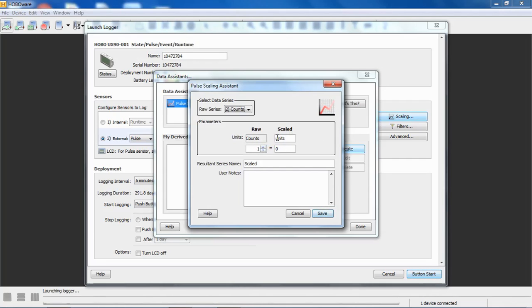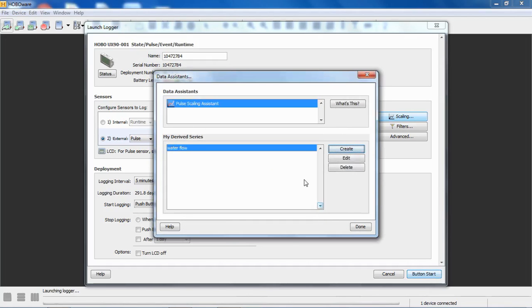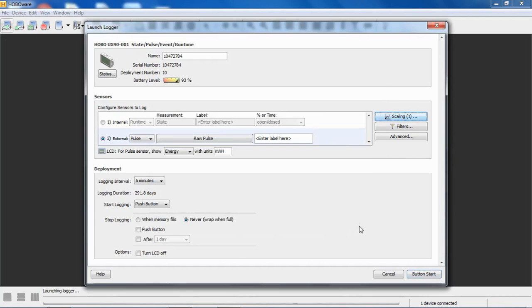What you can say is your raw value: how many pulses equals how many of your scaled units or engineering units. For example, if you had a flow meter that outputs one pulse per gallon of water, you could say one pulse or one count equals one gallon. Then you could call this water flow, or just water, or whatever you want to call it, and click on Save and done.